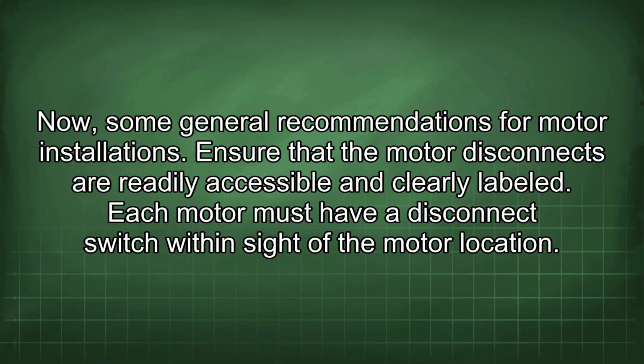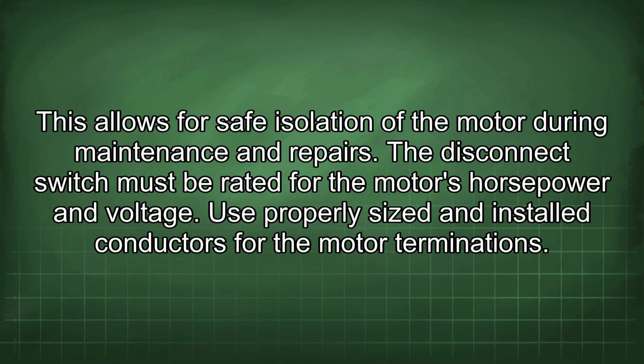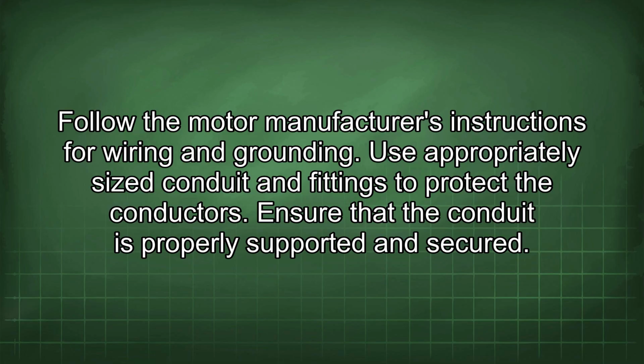Now, some general recommendations for motor installations. Ensure that the motor disconnects are readily accessible and clearly labeled. Each motor must have a disconnect switch within sight of the motor location. This allows for safe isolation of the motor during maintenance and repairs. The disconnect switch must be rated for the motor's horsepower and voltage. Use properly sized and installed conductors for the motor terminations. Follow the motor manufacturer's instructions for wiring and grounding.